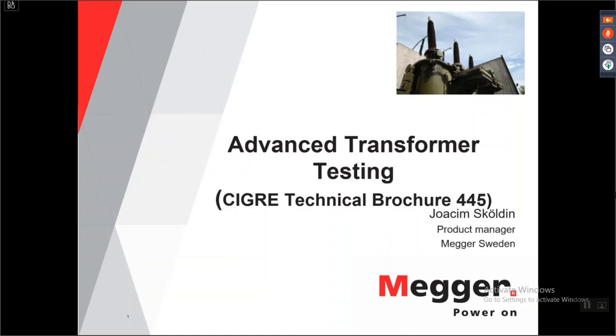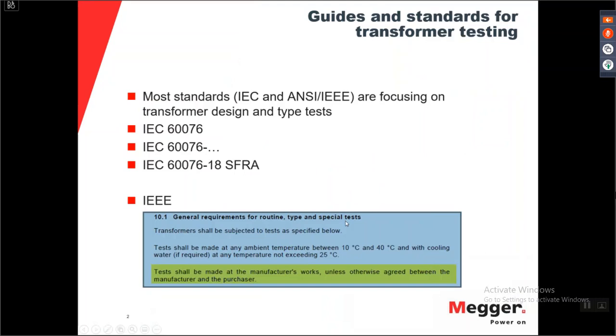So we were discussing standards and how you should test the different transformers. The most common standard is the IEC 60076, where you have -1, -2, and so on, and -18 happens to be the SFRA standard. The problem with these IEC standards is that they define that all the tests shall be done at the manufacturer's works, which means it's not really applied for the field.